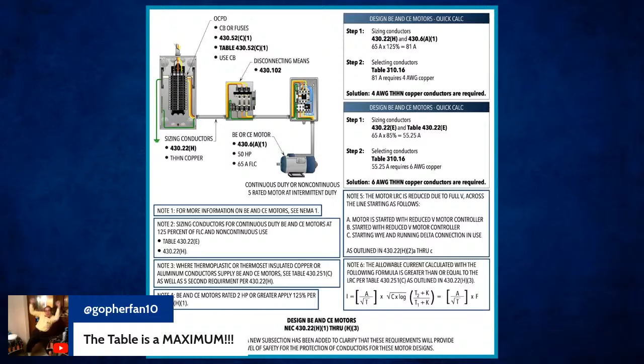Yeah. Or starting 100%. That would be a minimum starting point right there. Now, I can go down below that if it'll allow the motor to start, but I'm setting up a point here. So I've got a minimum, next, and maximum size. Now, before I go any further, I'm going to give another example on something that I want everybody to pay attention to. If I go over and I look at 440.22, that's where you're going to get your application and setting. And what does it say over there?